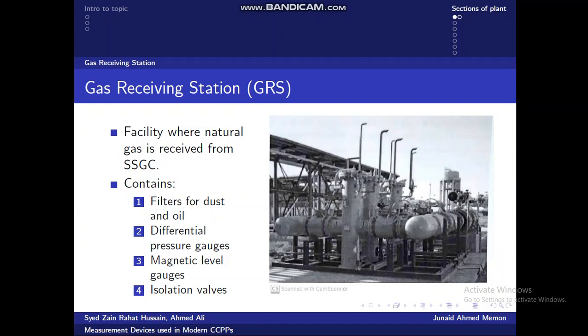So the GRS, or the gas receiving station, is one of the first parts of the plant. It is the place where natural gas is received from SSGC, or the Sui Southern Gas Company. The gas is then metered, and then it is filtered for supply to the gas turbines. So the filters that are present include scrubbers, which remove large dust particles, and other filters that remove oil that may be present. This oil can be very dangerous during the gas compression stage, which is the next one.